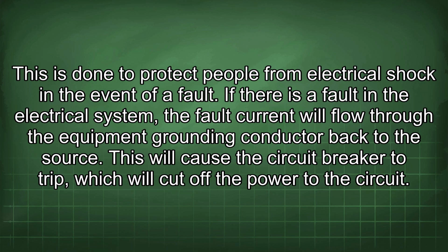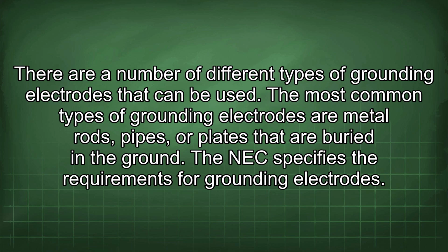If there is a fault in the electrical system, the fault current will flow through the equipment grounding conductor back to the source. This will cause the circuit breaker to trip, which will cut off the power to the circuit. There are a number of different types of grounding electrodes that can be used. The most common types of grounding electrodes are metal rods, pipes, or plates that are buried in the ground.